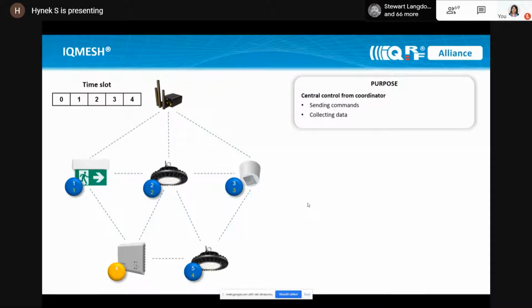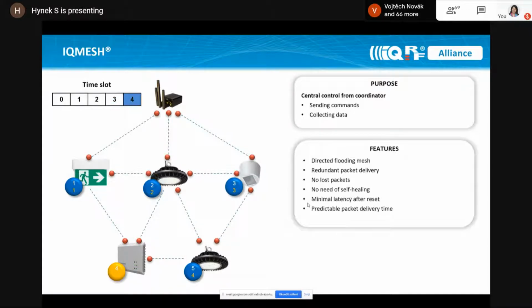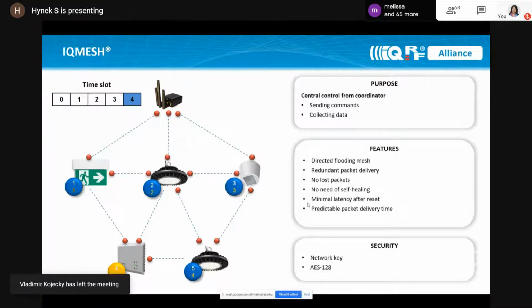In general, the purpose of IQMesh basic communication is to send commands to devices and collect data. Every device has a dedicated time slot, and in its time slot it simply repeats the message it received from the previous device. That brings the following positive features of IQMesh: first, it's based on directed flooding, and security again is based on AES 128, with a network key unique to every network used to protect the data sent in IQMesh.